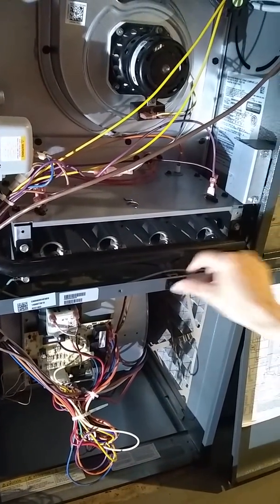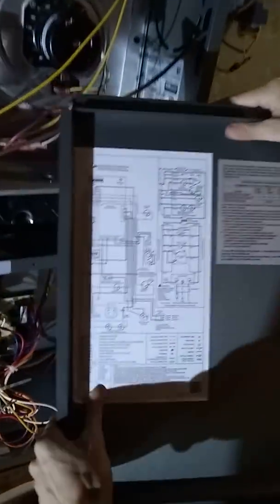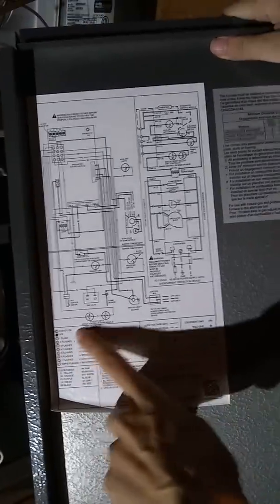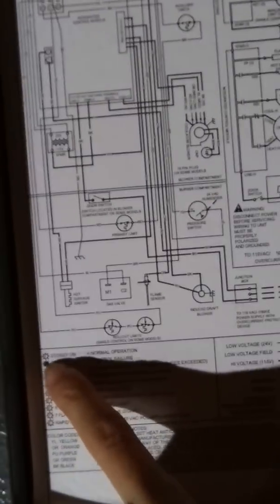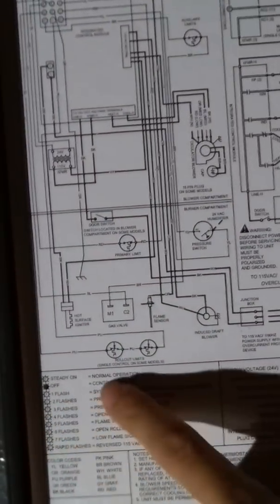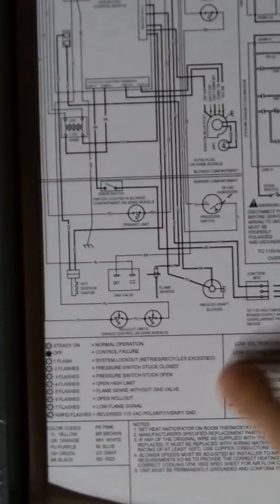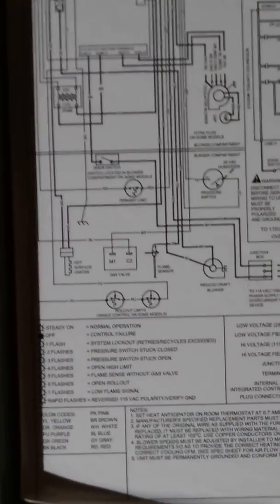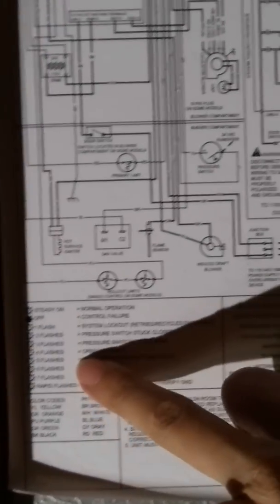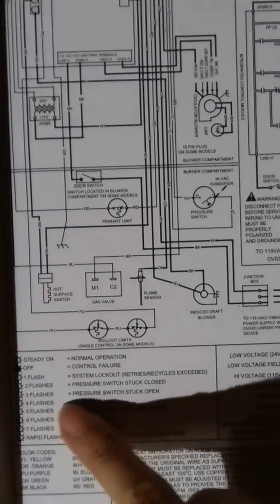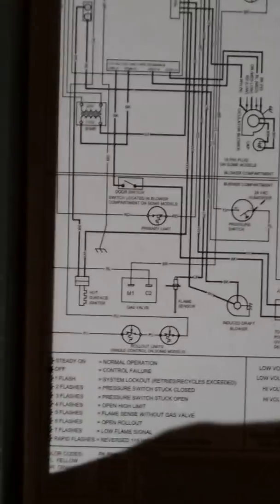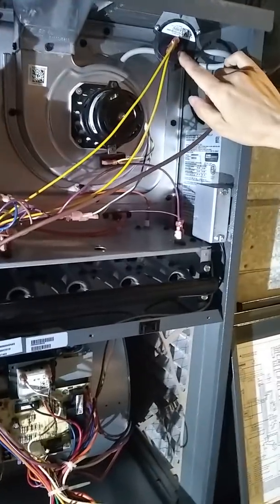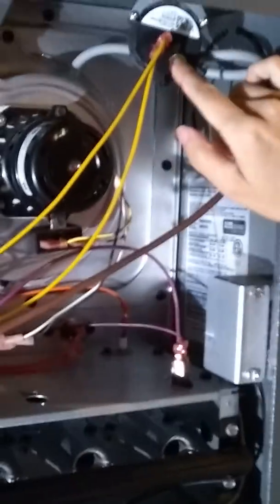Now let's go back to this panel and look at here. There are some manual information about this light. If it's steady on, it means normal. If it's off, there's some big problem. If it's flashing, the computer is working but can detect some signal that's not working, and gives this signal. Three flashes means pressure switch stuck open. So let's look at the pressure switch.